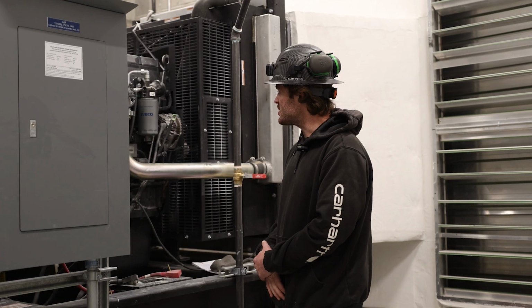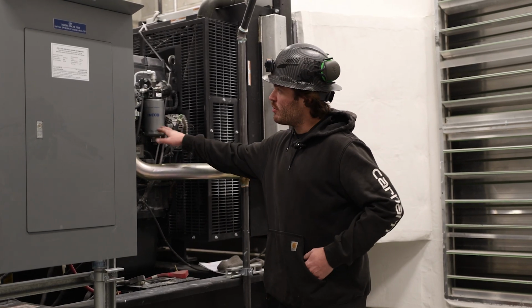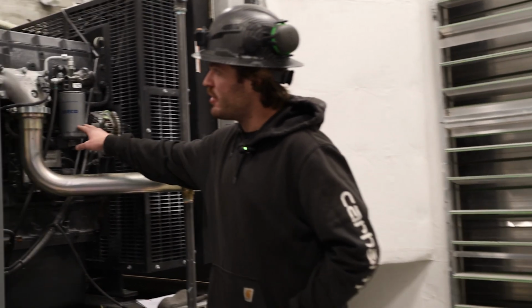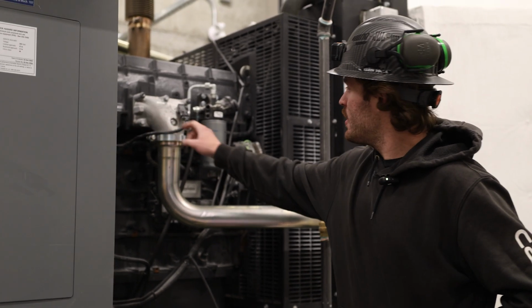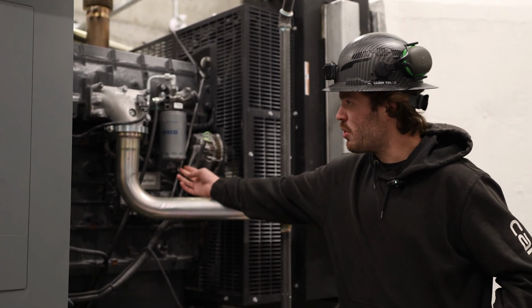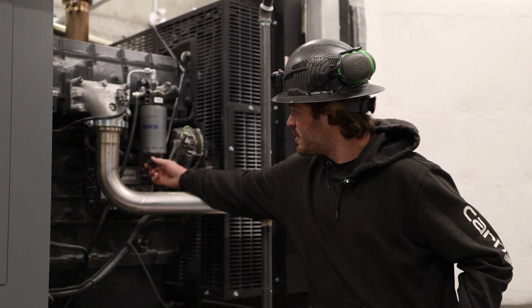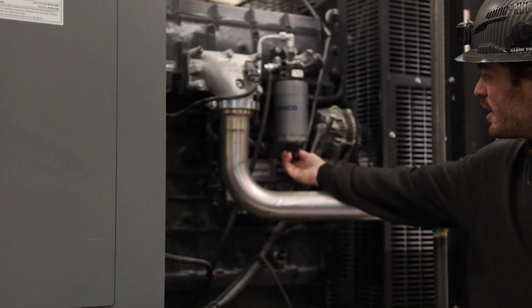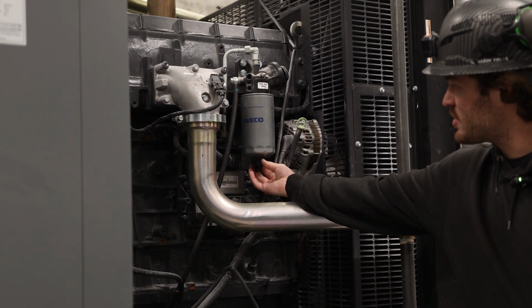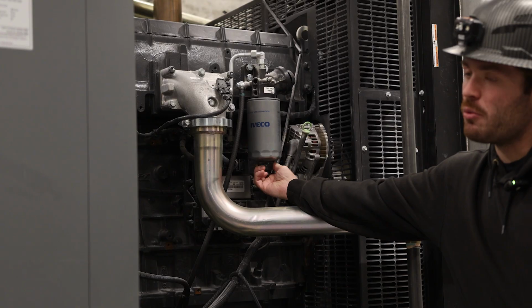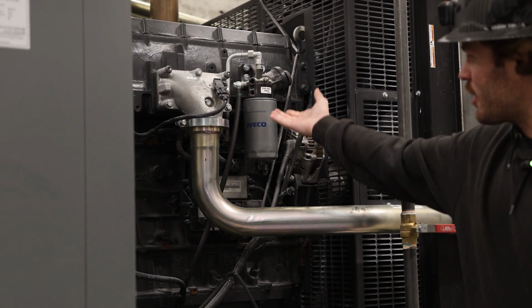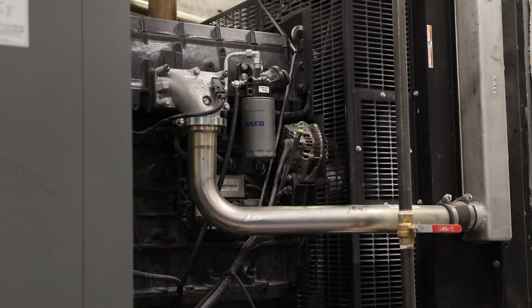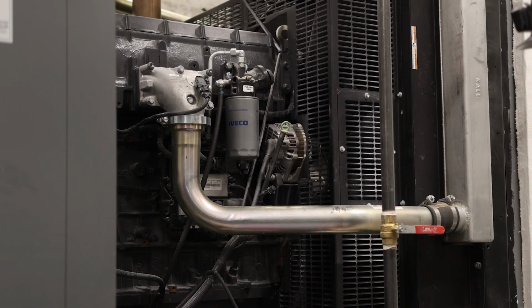Moving up on the gen set itself, on this side we have our fuel filtration. It has a primary and a secondary fuel filter. The primary fuel filter also has a water separation to it. On inspections and testing, it's worth unscrewing it slightly, and any water that was in the fuel that got caught up in the filter will drain out. It's to keep water from getting into our fuel injection system.